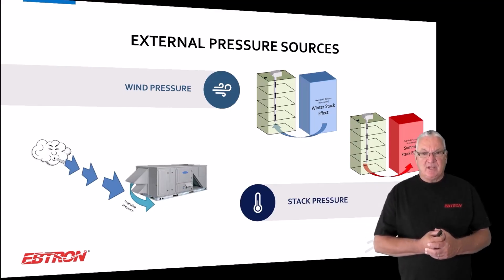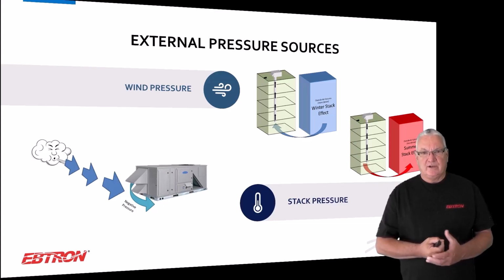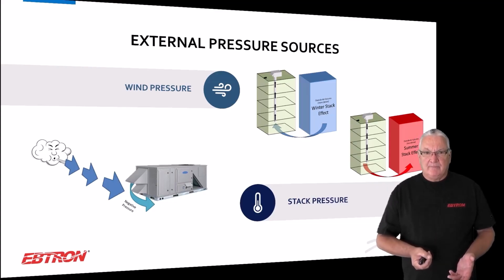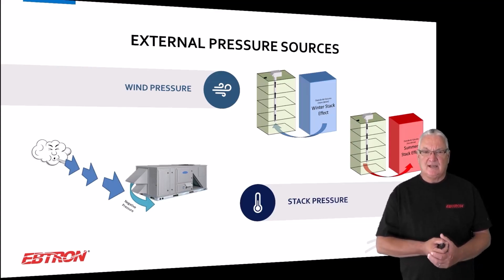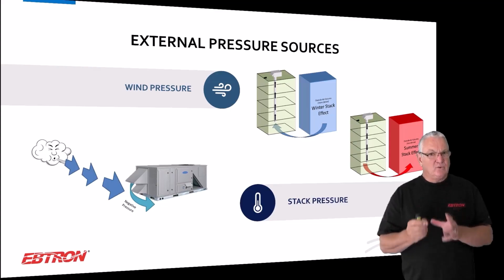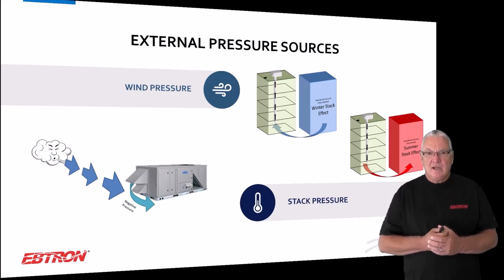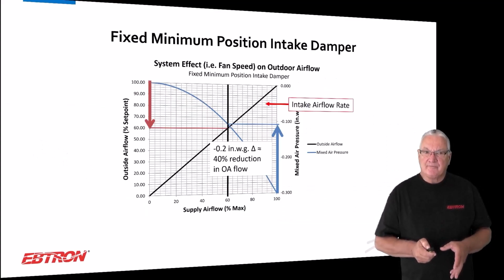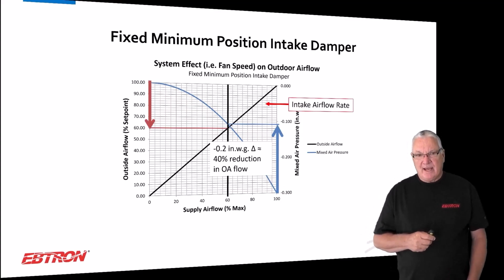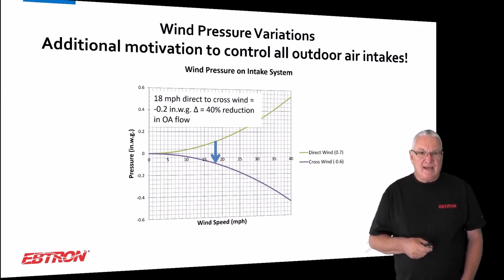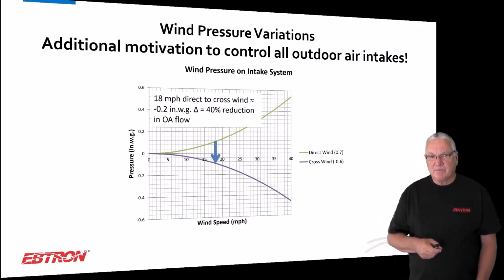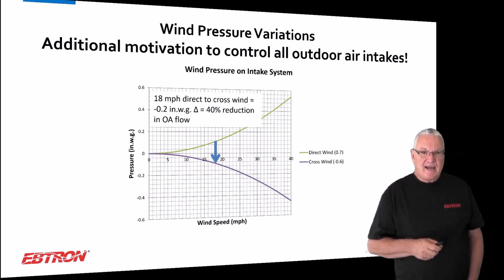The illustration on the right side of the screen is, hey, I have an air handler on the roof serving the first floor. Well, it's only serving the first floor, so the return duct's a big hole in the building that's connecting the first floor to the downstream side of the intake damper. So when you go from winter to summer, you have stack pressure problems, not like you think of for affecting floor pressure, but just for affecting what's going on at the air handler. And we're going to show you it's not just high rises, okay? So when you go back to this slide that we had and looked at this 0.2 of an inch change causing a 40% reduction, you could get the same 0.2 of an inch change on the other side of the damper, okay, simply by having the wind change.